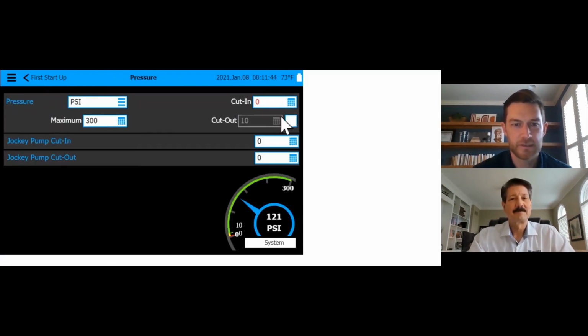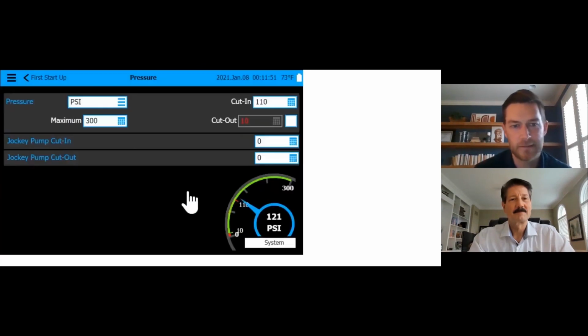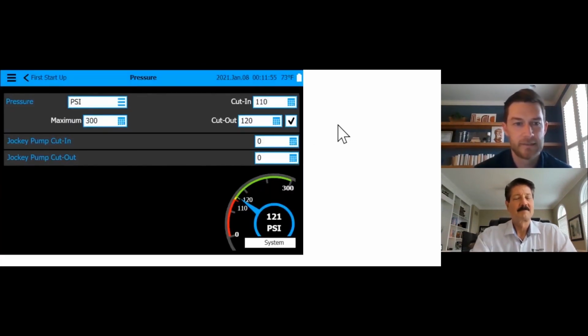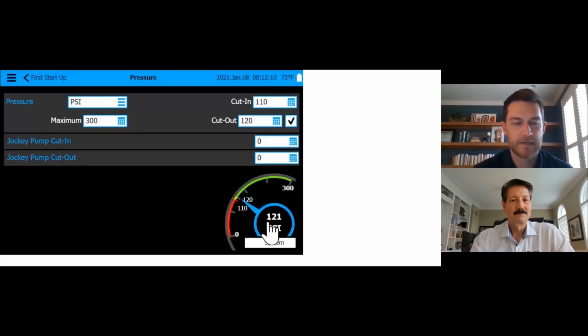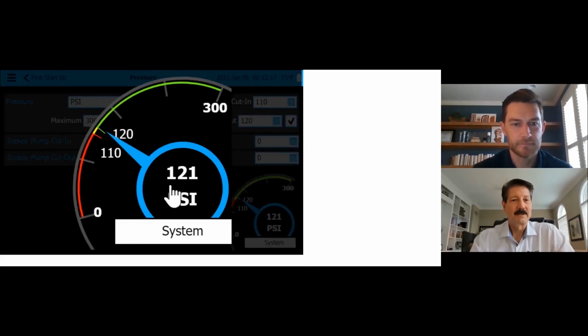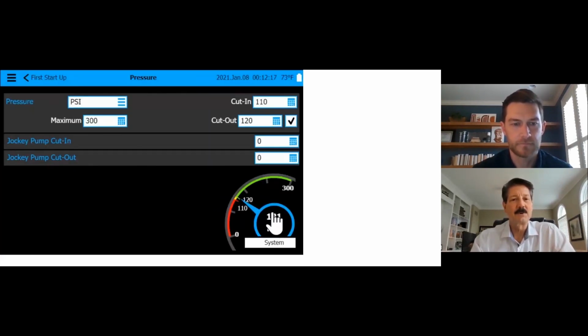This is where you'll set your cut in. And like Marty said, on the electric, you have the option to where, if you enter your cut in point, it'll automatically populate the cutout 10 PSI higher. If you want to modify that, you can check that box and change it. It also gives you the opportunity to put in your jockey pump cut in and cut out as well. And again, that's not controlling the jockey, just for statistical purposes, not diagnostic purposes. It's not required.